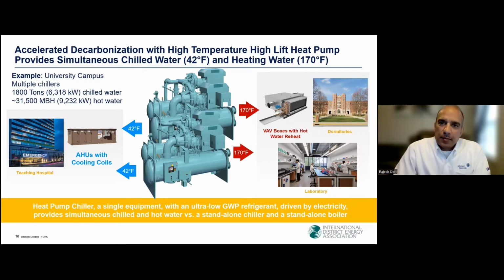So due to the principle of compounding explained in the previous animation, the unit is delivering simultaneous 42F or 6 degrees Celsius chill water for meeting that hospital's cooling load and 170F or 77 Celsius for taking care of the heating load. Such systems can also be extended and have been successfully deployed, I should say, wherever coincidental cooling and heating loads exist, such as in hospitals, airports, district heating, and industrial processes.